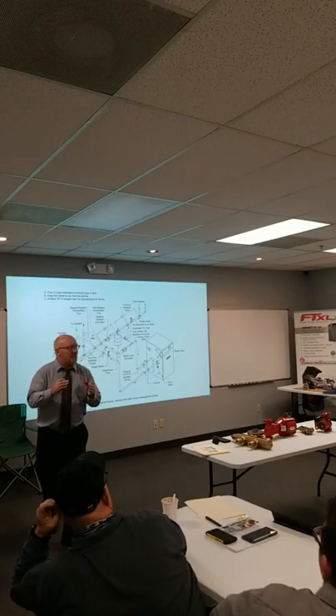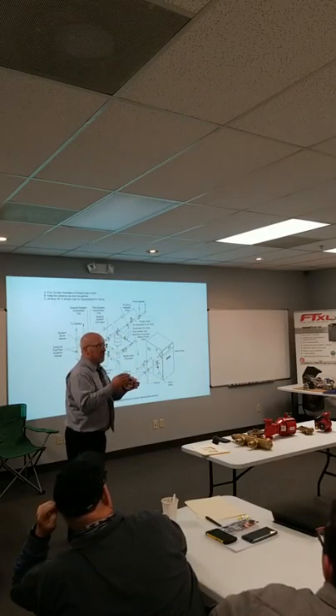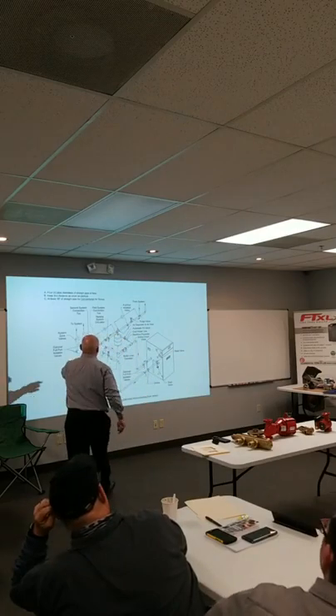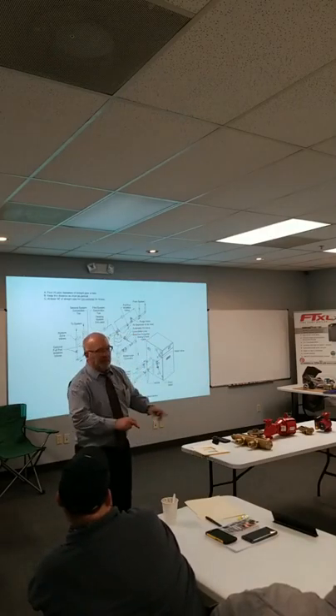But that's where the 12-inch comes in. It's 12-inch max no matter what pipe size you have. But the maximum is really 4 pipe diameters. So 1-inch pipe in the main, 4 times 1, 4 inches is the maximum. If you can get them closer, get them closer. The closer the better, is absolutely it.